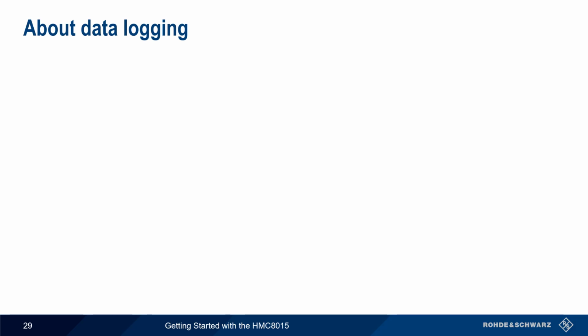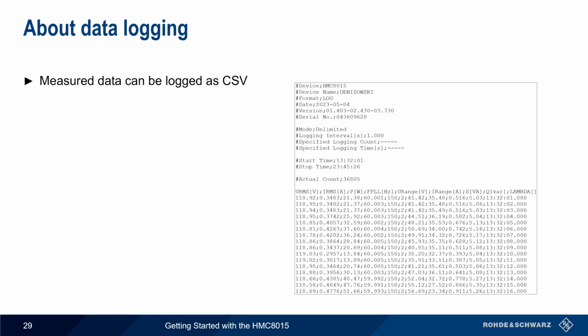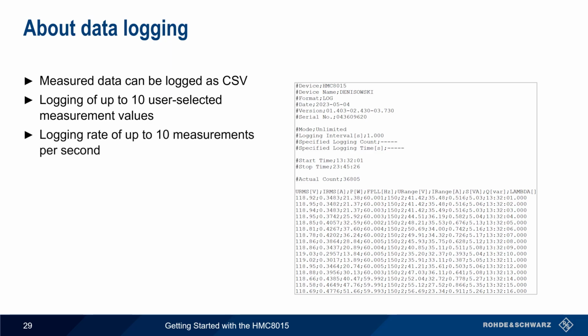Next, let's talk about data logging. Measured data can be logged in the form of a CSV, or comma-separated value, file. Up to 10 user-defined measurement values can be logged, and the logging rate can be configured up to a maximum of 10 measurements per second. Logging can be controlled in 3 different ways.